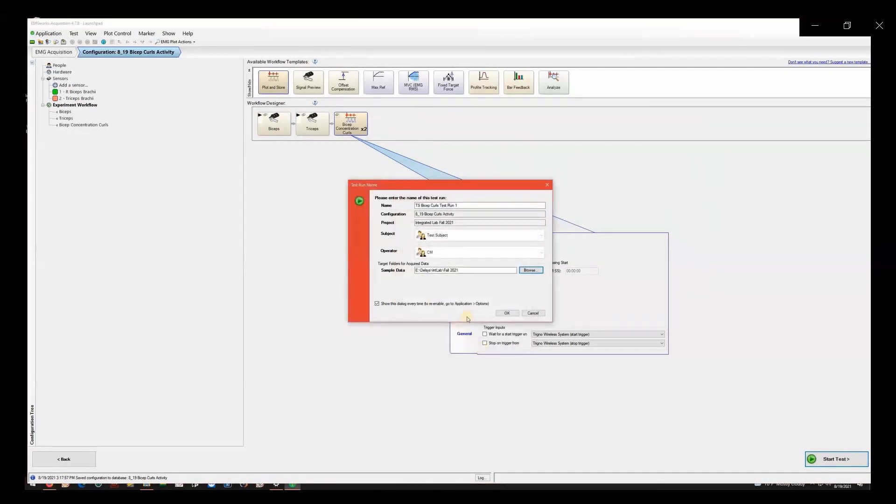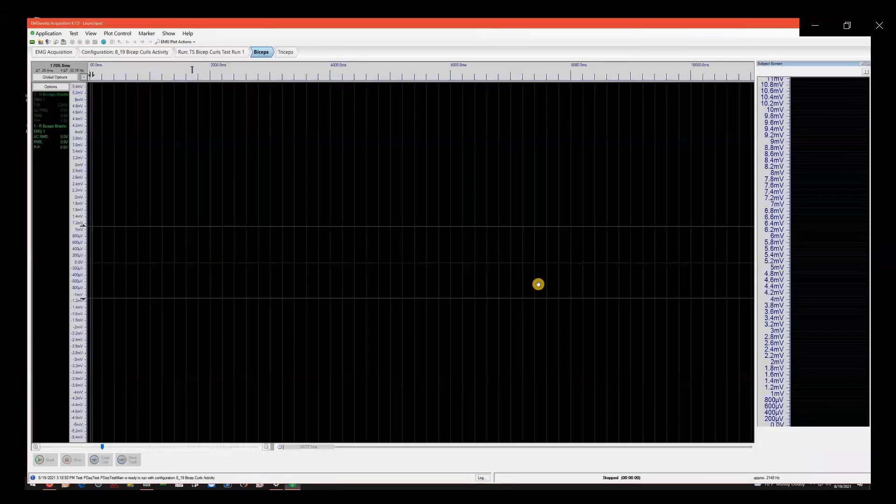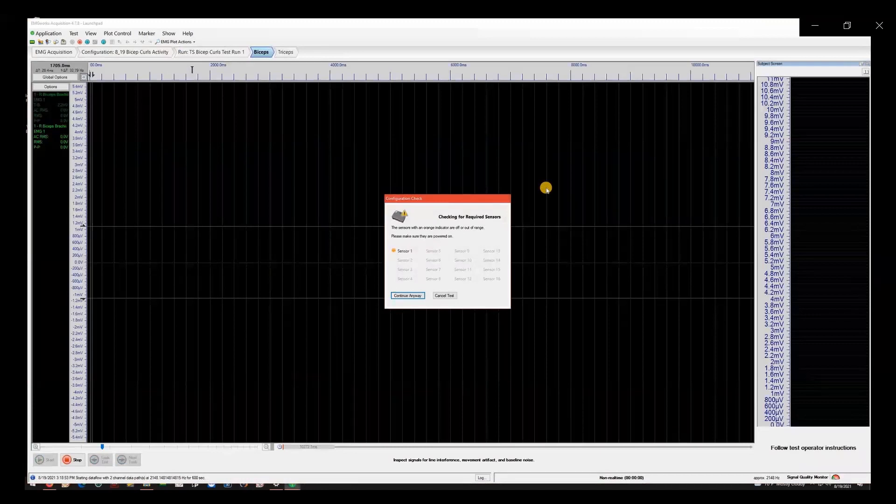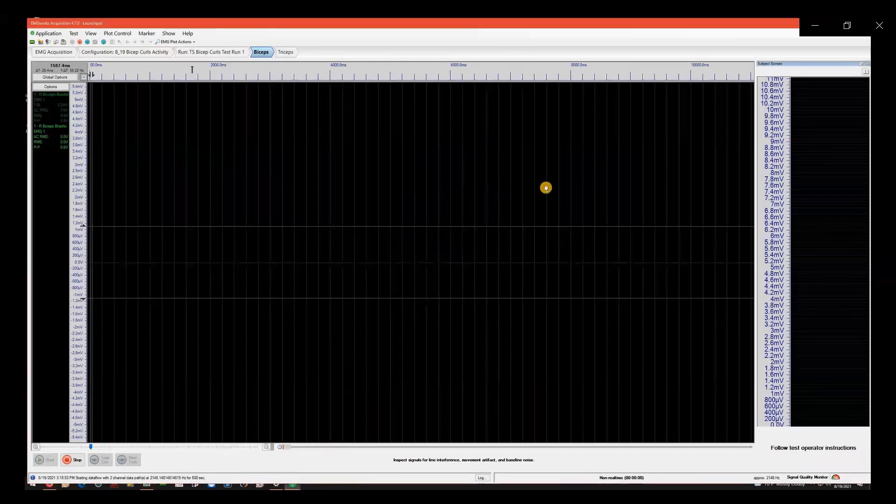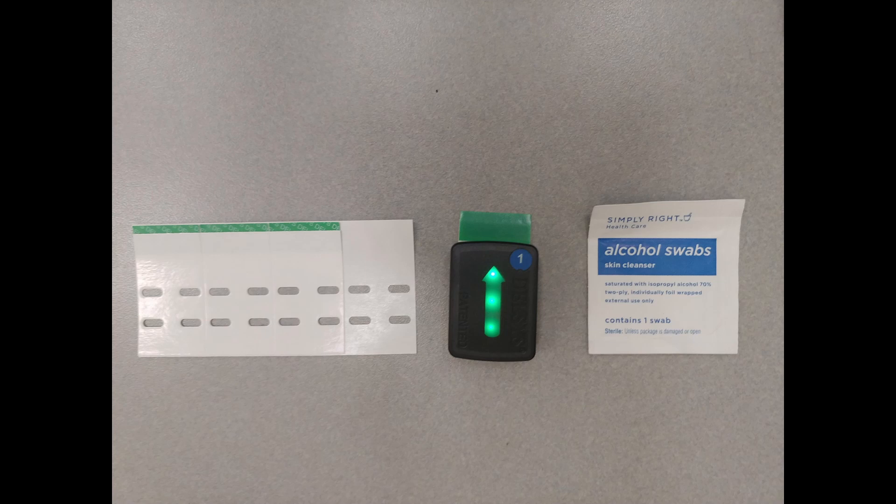In this example, we are starting with the first activity, which is the right biceps check. In the Sensor Activation Procedure, there will be pop-ups showing which sensors are needed. First, remove the sensor from the base station. While the sensor is glowing white, hold the sensor against the dark green circle on the white tag in the middle of the base station, with the arrow pointing downwards. The sensor will become green, then continuously blink. This sensor is now ready for data collection.